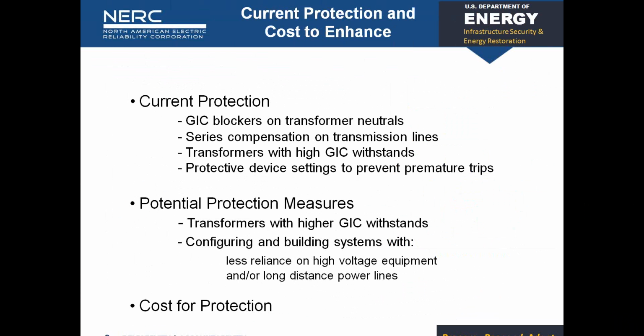Those are not inexpensive. Some of the slides from one vendor quoted about $125,000. I just saw a recent study looking at protecting all of BPA, and it came out to about $900,000 per substation, assuming you protect about two transformers per substation — so the blocker may be $450,000 each. That's not insignificant. If a transformer costs $2 to $7 million for some of the large power transformers, that's still a big chunk of change — spending almost $500,000 to protect one, including hardware, installation, and software. The hardware itself doesn't cost that much, but altogether it's quite a bit of money.